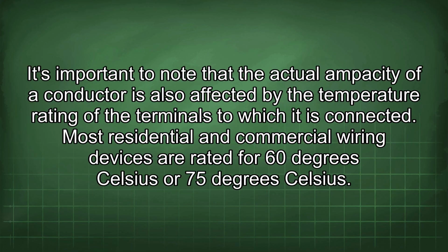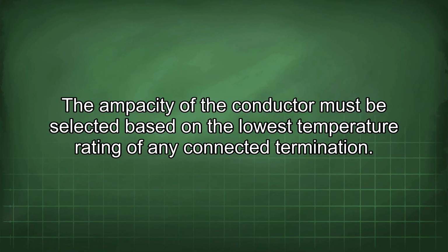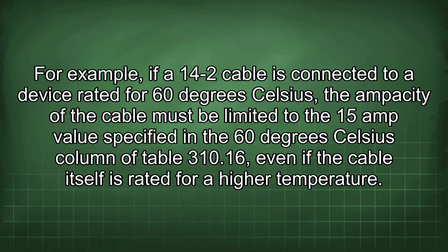It's important to note that the actual ampacity of a conductor is also affected by the temperature rating of the terminals to which it is connected. Most residential and commercial wiring devices are rated for 60 degrees Celsius or 75 degrees Celsius. The ampacity of the conductor must be selected based on the lowest temperature rating of any connected termination. For example, if a 14-2 cable is connected to a device rated for 60 degrees Celsius, the ampacity of the cable must be limited to the 15 amp value specified in the 60 degrees Celsius column of Table 310.16, even if the cable itself is rated for a higher temperature.